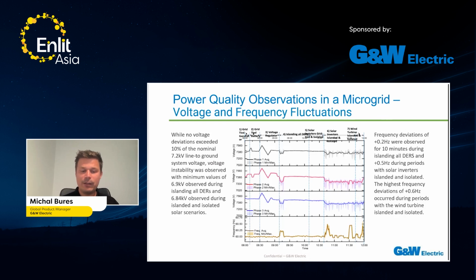So as expected, power quality issues were observed. First one, voltage and frequency fluctuations. As you can see on the first 3 charts from above, voltage fluctuations were observed, probably luckily not exceeding 10%, but visible mainly during the DERs' islanding, causing drops down to 6.84 kilovolts. So we have nominal 7.2 line to ground. Same as the frequency deviations visible at the bottom of the charts, where we have a maximum difference of 0.6 Hz during the same conditions.